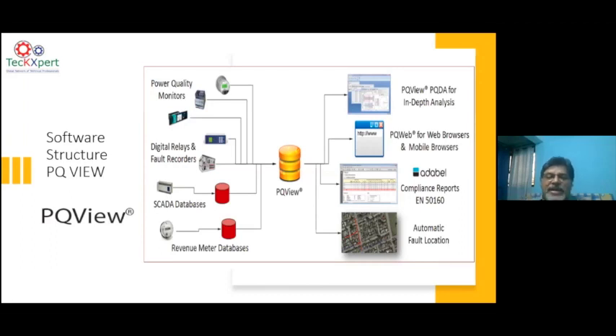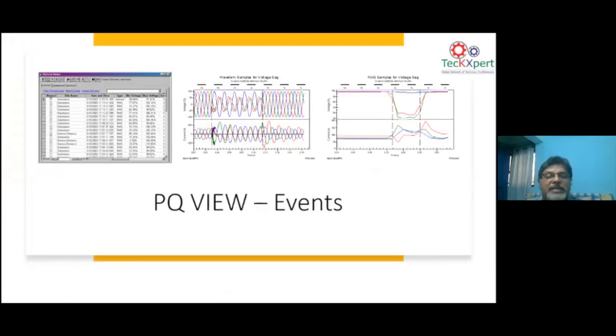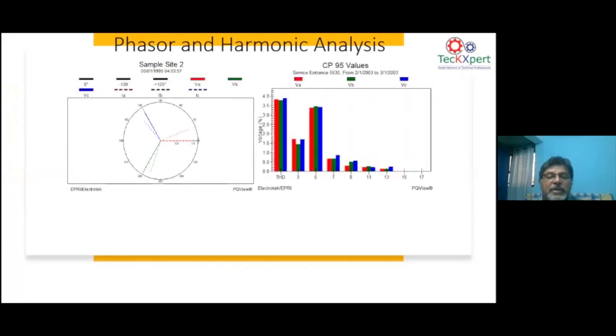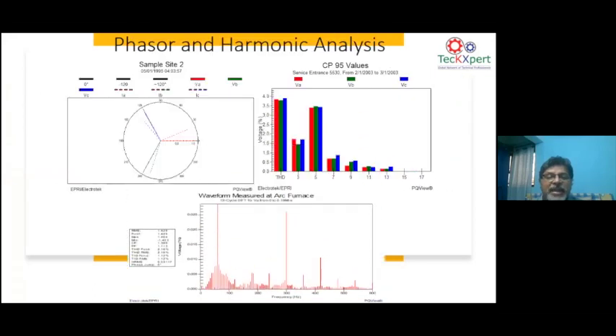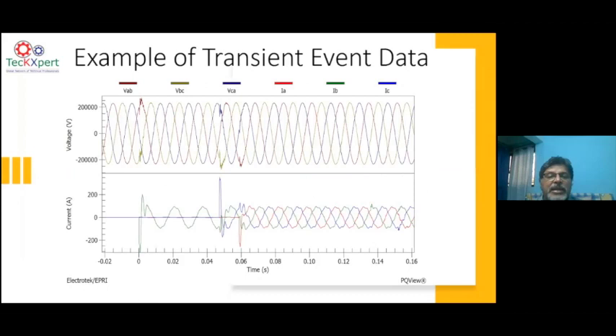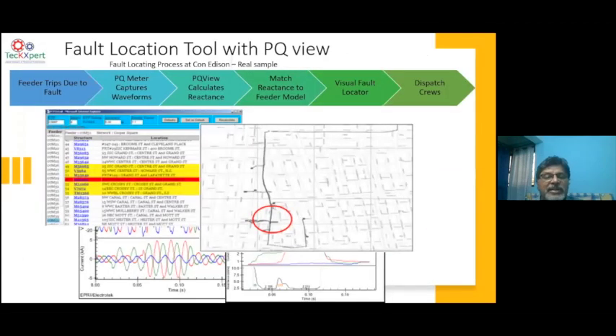That means all the data will be in one point. In a substation, if you install this, let me bring a typical example. When you have these multiple devices, this is how the events are captured by the continuous event monitoring. I will bring an interesting case here, where these are various types of events captured by the continuous monitoring. So this is a case where you can locate the fault by using this sort of software.